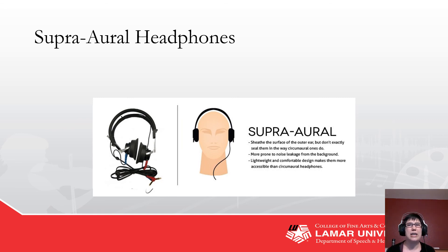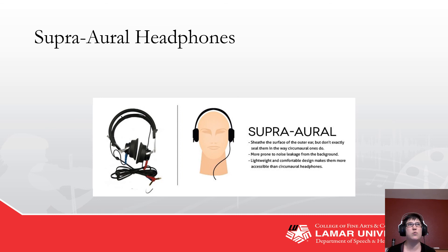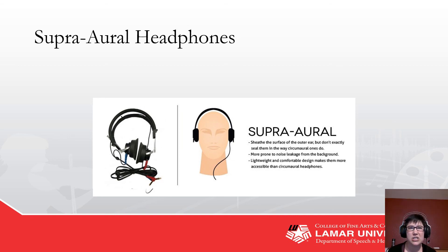In the clinic team channel, there are videos on how to put on different transducers — after you finish this video, go check those out. Supra-aural headphones are widely considered the reference standard because that's what we started out with and what we compare everything against. They're relatively inexpensive, very sturdy, keep calibration well, and are good for even malformed or deformed ears.